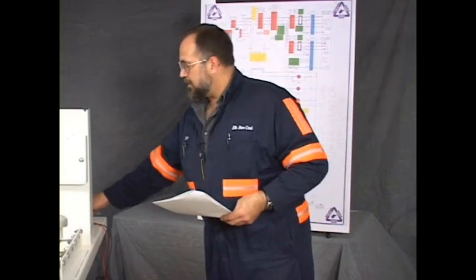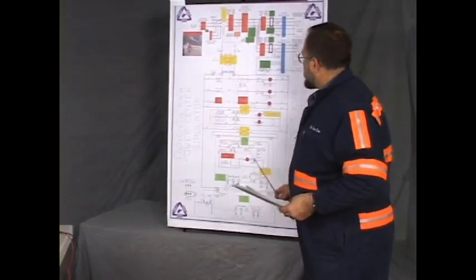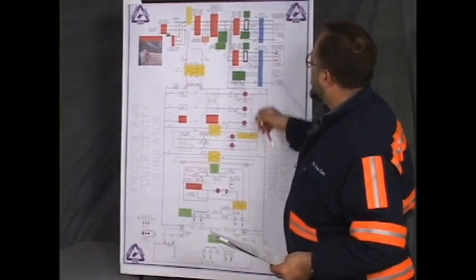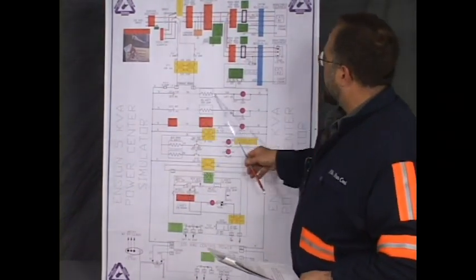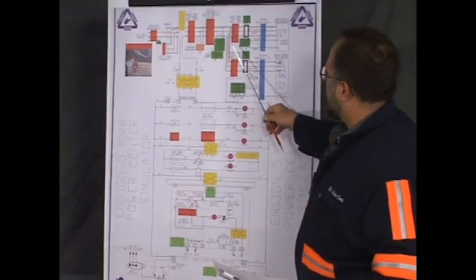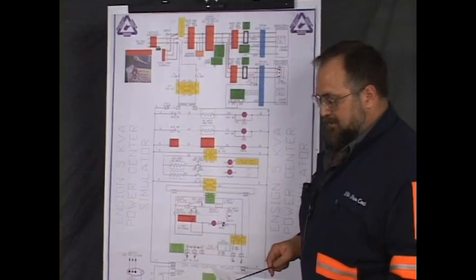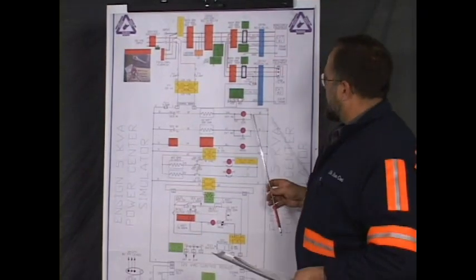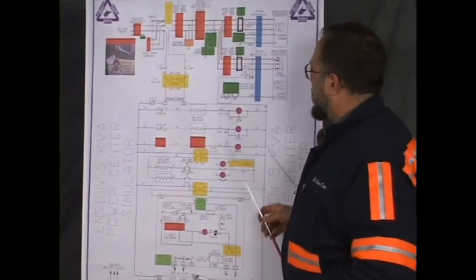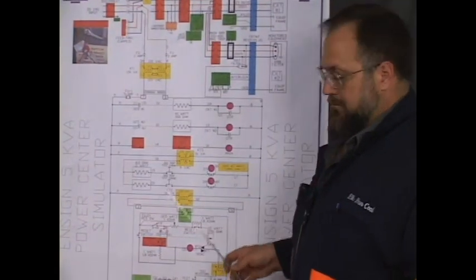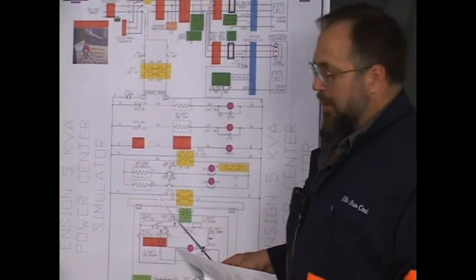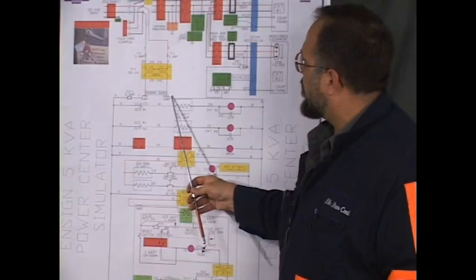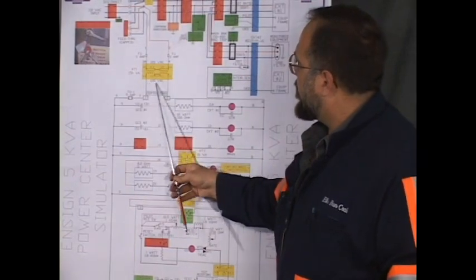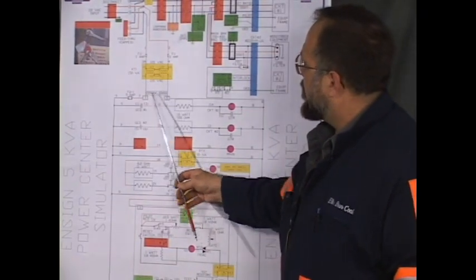These problem cards really give you a lot of information if you're discerning and pay close attention. Circuit number 1 breaker can't be set. This is the circuit that controls circuit number 1 breaker. It says the UV won't pick up, so we know the UVR doesn't have power. It says that proper control voltage is present. We have control voltage here. The secondary is producing 120 volts. And it's present.